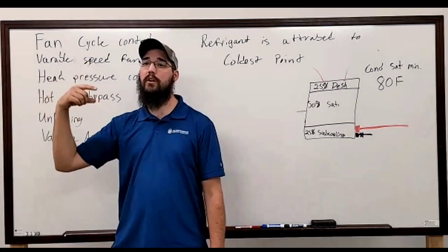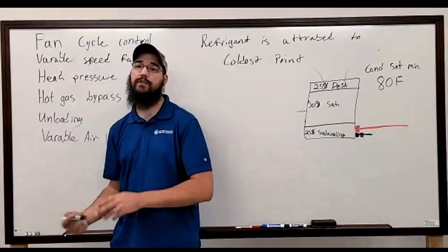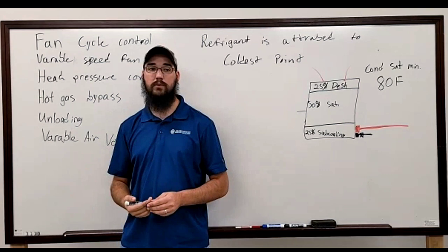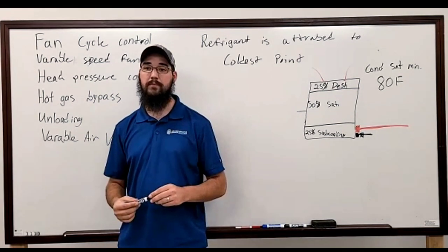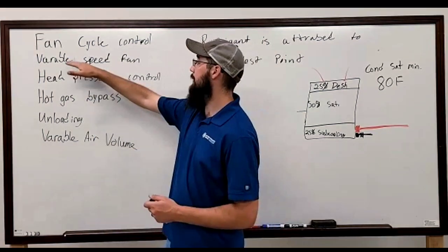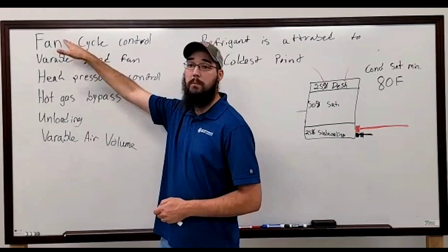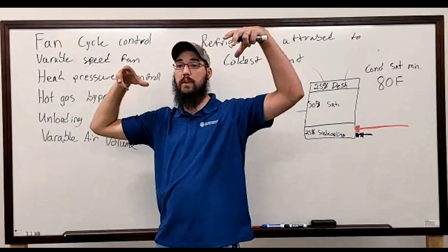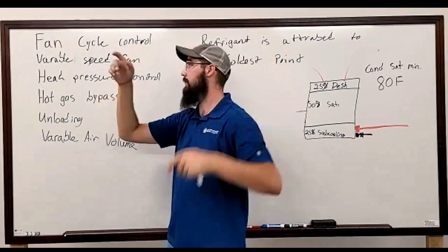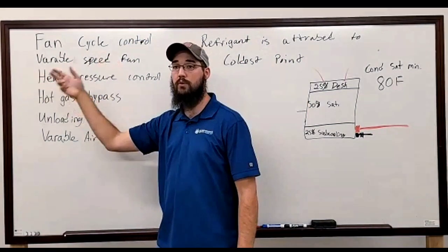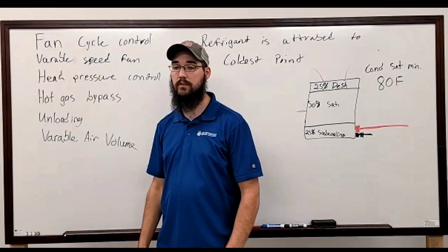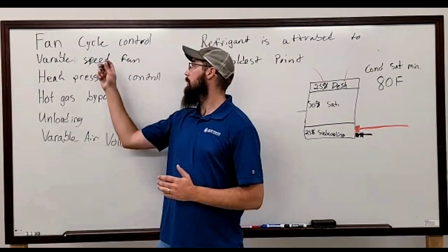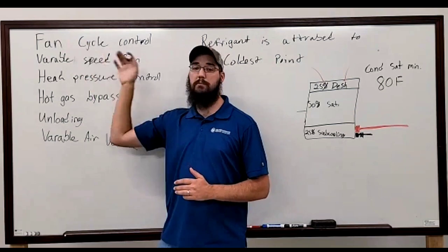Once you start getting into the bigger systems and really on the much heavier side, you'll actually start running into VFD controlled condenser fans. Yeah, it's very common. At that point, it'll be kind of a hybrid between the two. Half the fans, or maybe if you have 6, 4 fans will be run on fan cycling, broken out into 2 groups themselves. You'll have first stage fans, second stage fans, and then the other 2 fans left over will be variable speed. Very common to see these blended together.